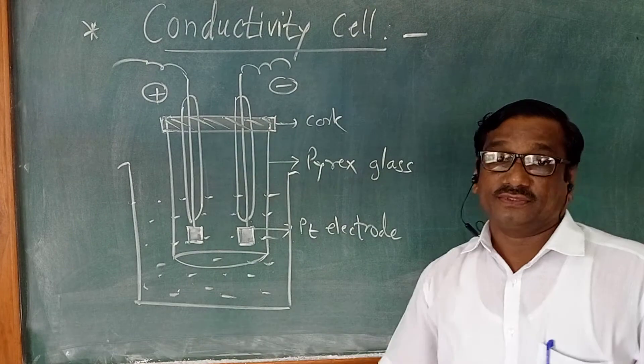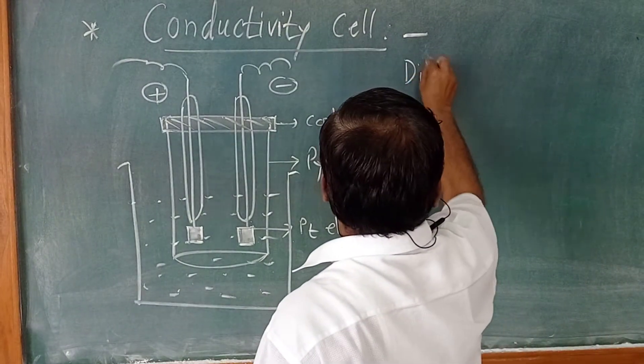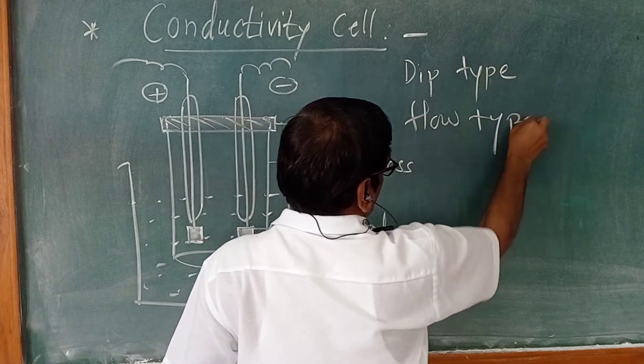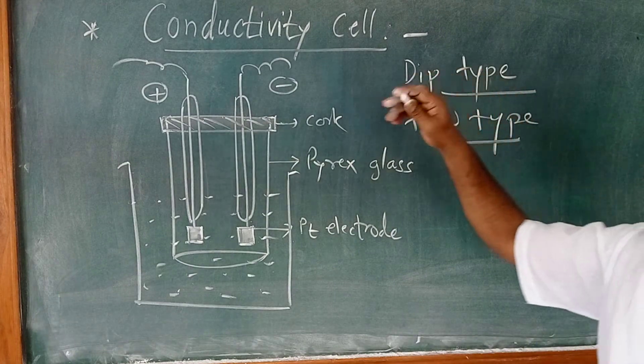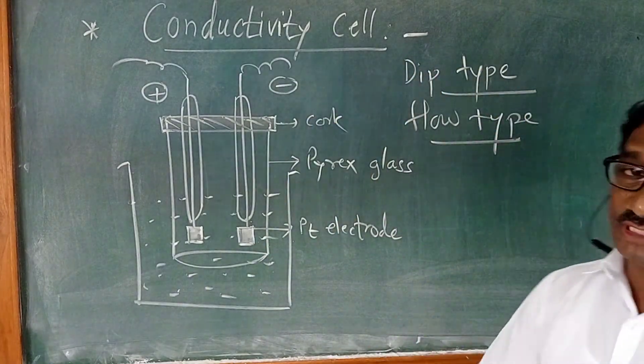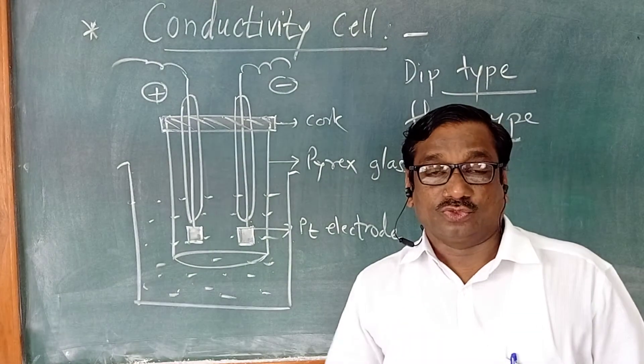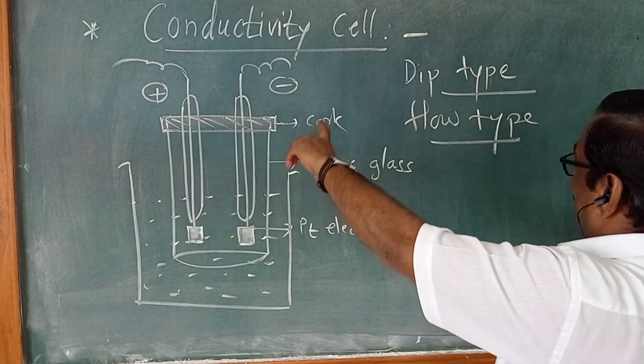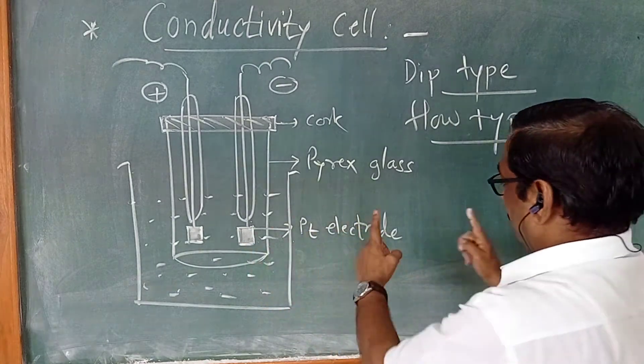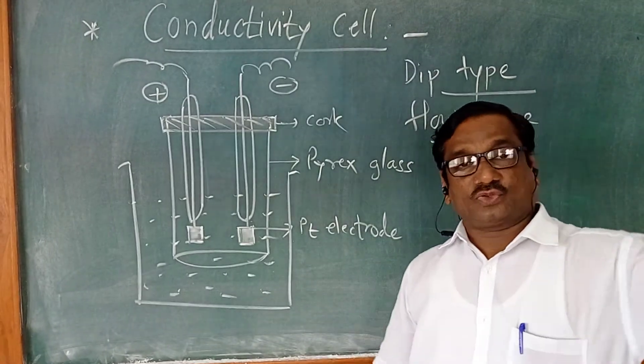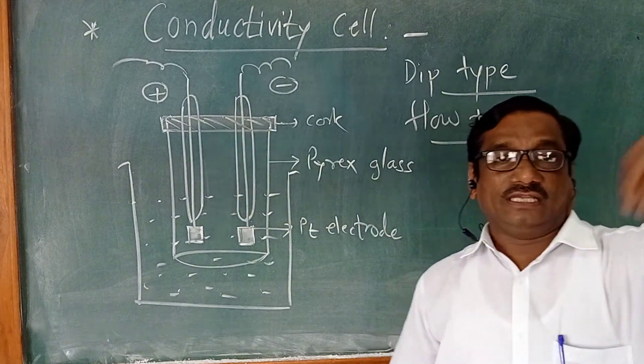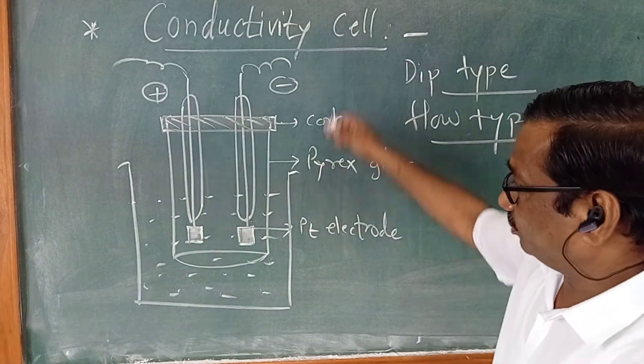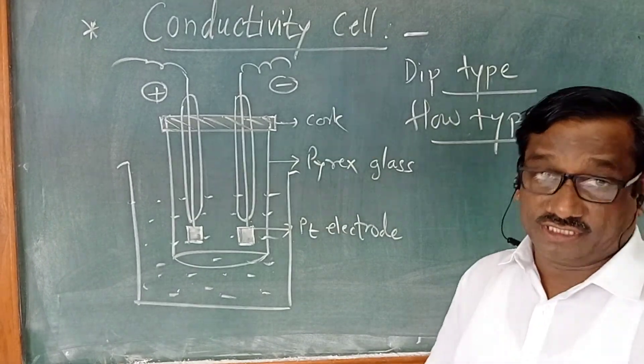This is the dip type of conductivity cell. The dip type is used in the laboratory, and the flow type is used in industry for continuous measurement. The flow type is essentially a U-shaped glass tube in which two electrodes are fixed and solution is flowing through that cell. There is an inlet and outlet, and you can measure the resistance or conductance of that solution continuously in the industry.